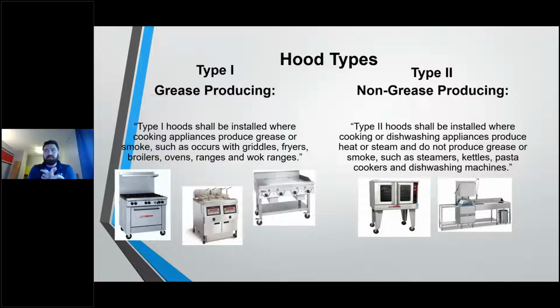Is there grease being produced in this system? Then, hey, it's a type 1 system that's going to require all of the components that we're going to talk about. UL 762 rated fan, fully welded grease duct, fire suppression system, everything that we'll go through here. Is it only condensate or is it heat? Well, then it's a type 2 situation, which is going to be a lower airflow rate, and your fans are going to be rated to a UL 705 listing.